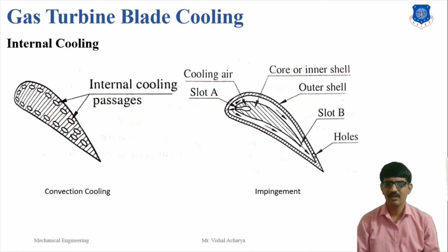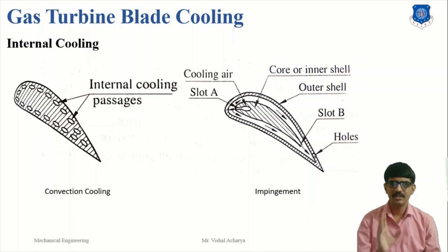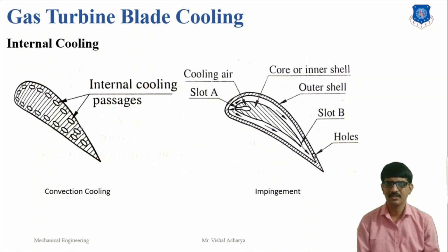Therefore, the blade and vane have to be cooled in order to lower the blade temperature. The objective of blade cooling is to keep the material temperature at a safe level in order to ensure longer creep life and low oxidation rate. Cooling air at around 650 degrees Celsius is extracted from the compressor and passed through the airfoils. With the hot gases and the cooling air, the blade temperature can be brought to approximately 1000 degrees Celsius, which permits reliable operation of the turbine.